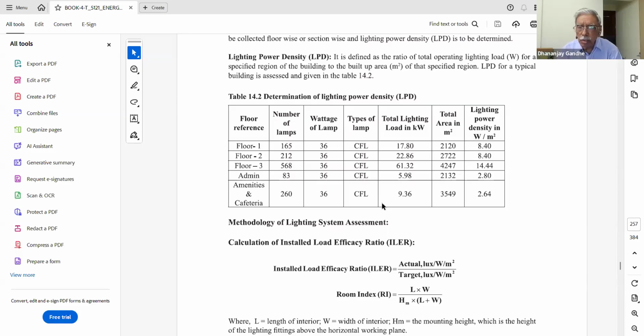So you take the total wattage and the total area. It's the division of wattage by area. So floor 1, 17.8 kilowatt. Again, work out wattage, that is 17,800 watts, divided by the area, 2120. This division works out to 8.4. So the lighting power density works out to 8.4.